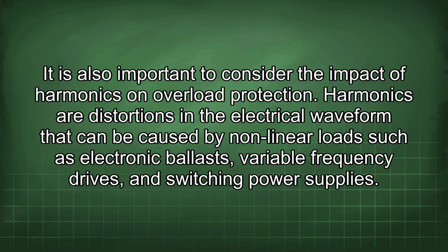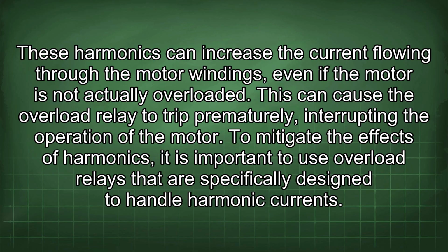It is also important to consider the impact of harmonics on overload protection. Harmonics are distortions in the electrical waveform that can be caused by nonlinear loads such as electronic ballasts, variable frequency drives, and switching power supplies. These harmonics can increase the current flowing through the motor windings, even if the motor is not actually overloaded. This can cause the overload relay to trip prematurely, interrupting the operation of the motor.